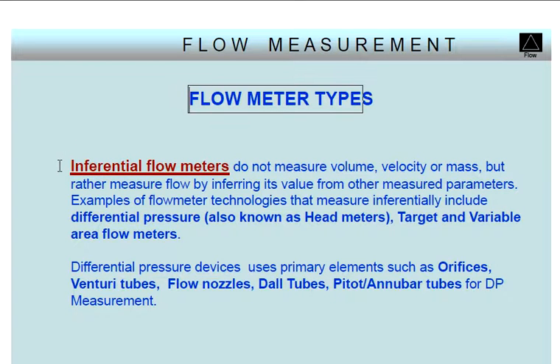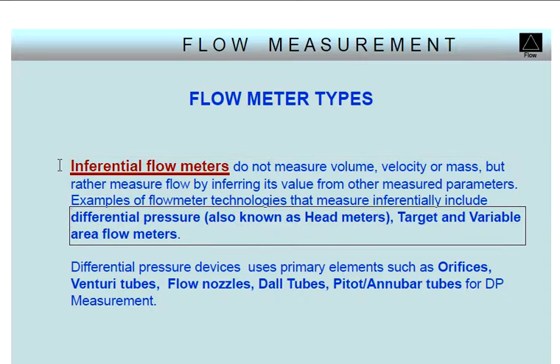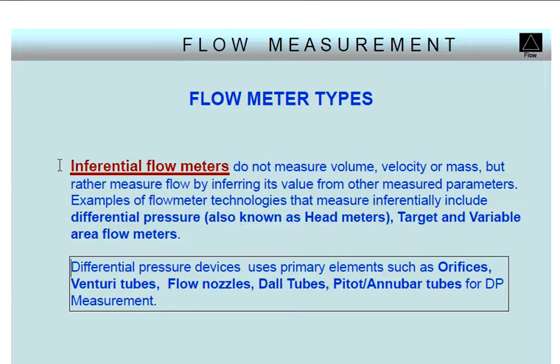Inferential type flow meters do not measure volume, velocity, or mass, but rather measure flow by inferring its value from other measured parameters. Examples of flow meter technologies that measure inferentially include differential pressure — also known as head meters — target, and variable area flow meters. Differential pressure devices use primary elements such as orifices, venturi tubes, flow nozzles, dall tubes, and pitot/annubar tubes for DP measurement.